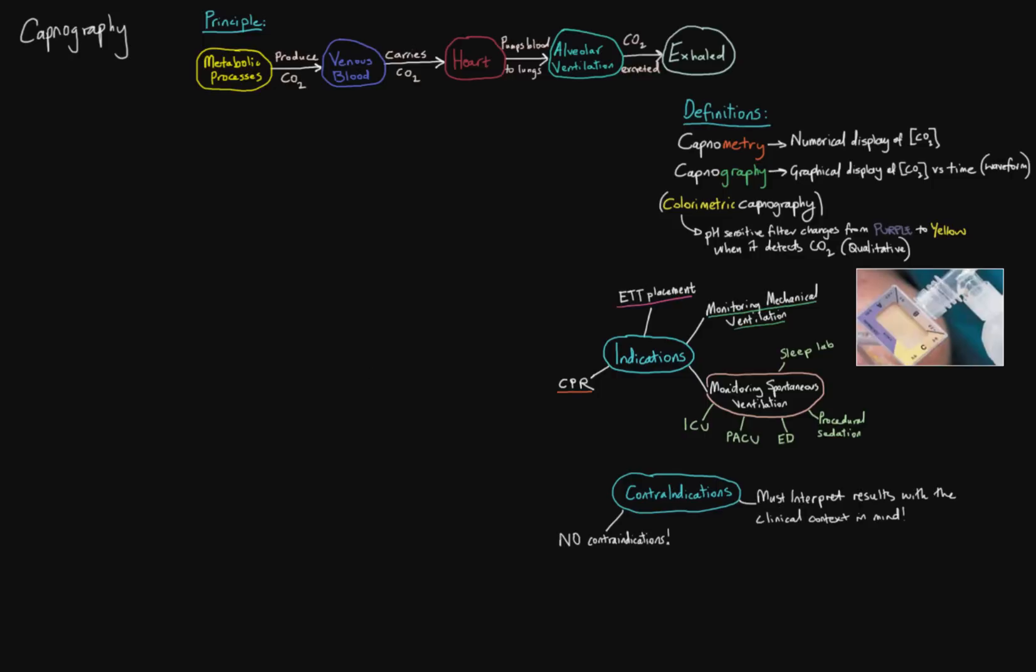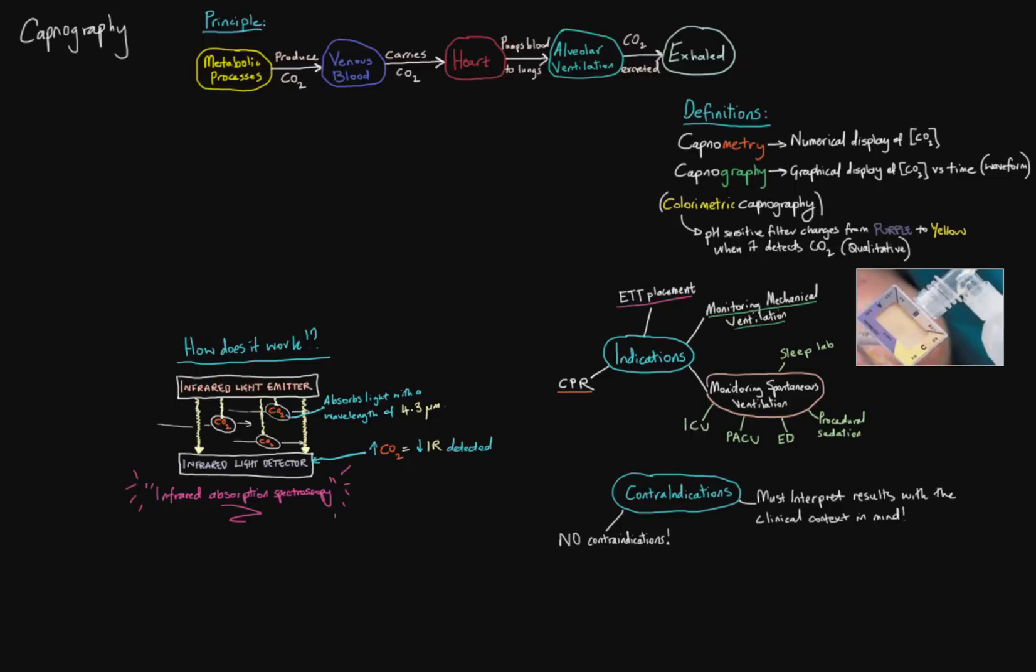So now that we've talked about some of the contraindications, how does it work? How do we actually measure CO2 in expired breath? I'm not a physics major by any means, but here's the basic principle of it. It's something called infrared absorption spectroscopy, which is a long winded phrase, but it is essentially an infrared light emitter will pass a certain wavelength of light, which happens to be 4.3 microns, and that gets picked up by an infrared light detector.